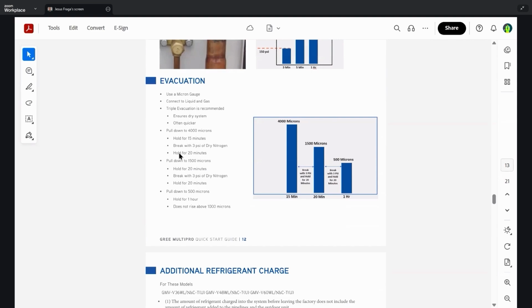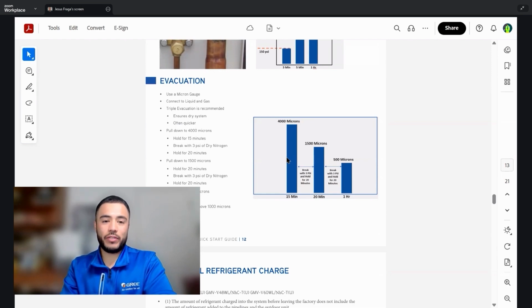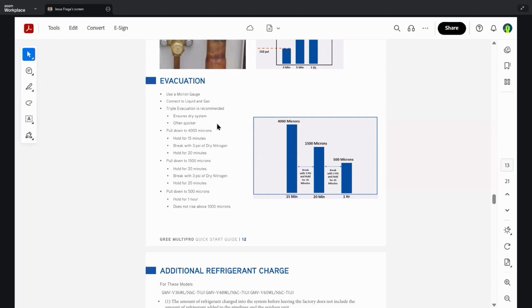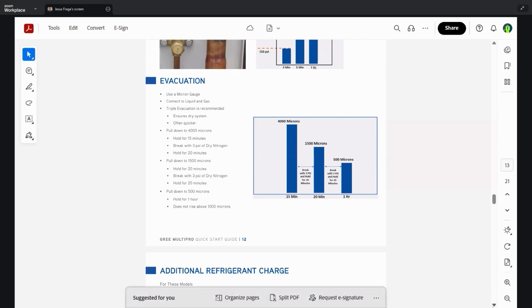The evacuation. You always use a micron gauge, because how are you going to know how many microns you have pulled down with your vacuum if you don't have a micron gauge? You can connect your liquid and gas and perform a triple evacuation. It's always recommended. It ensures that the system is dry, and it often is quicker once you verify that you do the triple evacuation. The first step is pull down to 4,000 microns, hold for 15 minutes, break with some dry nitrogen, hold for 20 minutes, pull down to 1,500 microns, hold for 20 minutes, break with 3 psi of dry nitrogen, hold for 20 minutes, then pull down to 500 microns and hold for an hour. If it does not rise above 1,000 microns, you're good.